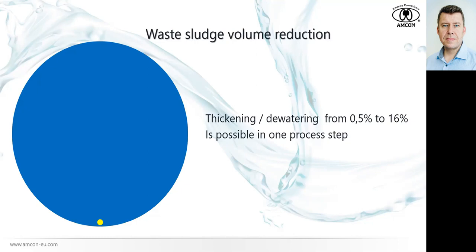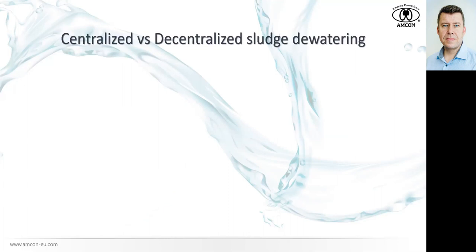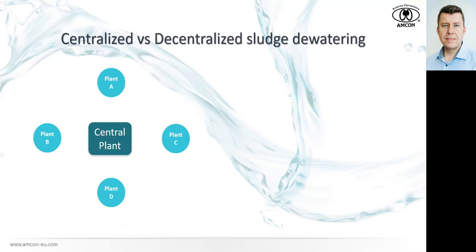Now let's talk about the difference between centralized and decentralized sludge dewatering. In the centralized scenario, we have wastewater treatment plants in different villages, cities, and towns, all sending their waste activated sludge to a central plant — usually next to a big city — where large installations like belt presses or centrifuges are installed. Due to high operating costs, they need to handle huge amounts of sludge to split the cost per cubic meter to a reasonable level.